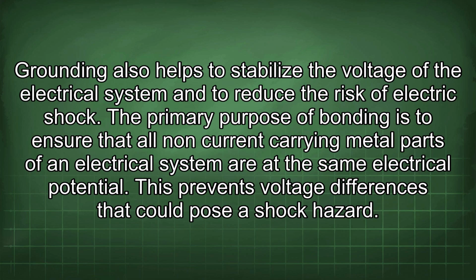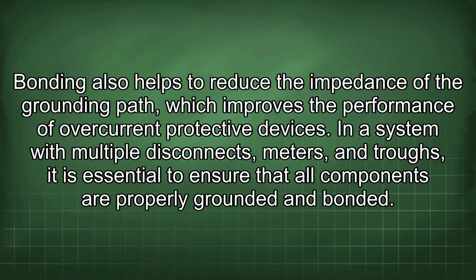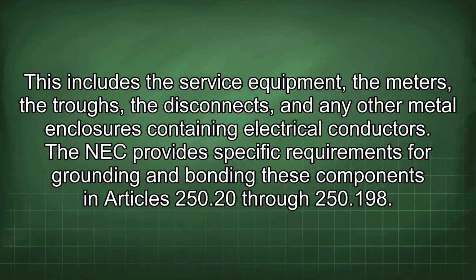This prevents voltage differences that could pose a shock hazard. Bonding also helps to reduce the impedance of the grounding path, which improves the performance of overcurrent protective devices. In a system with multiple disconnects, meters, and troughs, it is essential to ensure that all components are properly grounded and bonded. This includes the service equipment, the meters, the troughs, the disconnects, and any other metal enclosures containing electrical conductors. The NEC provides specific requirements for grounding and bonding these components in Articles 250.20 through 250.198.